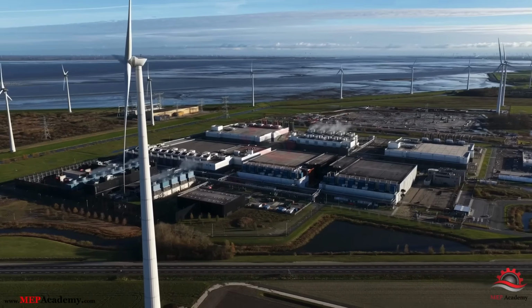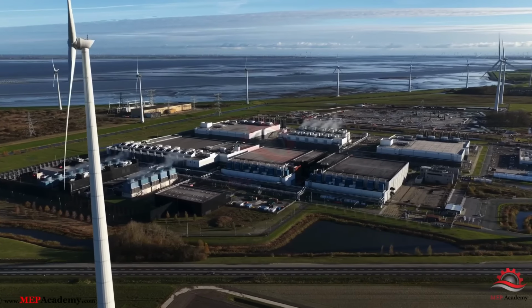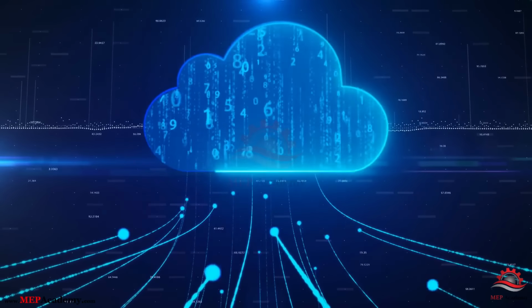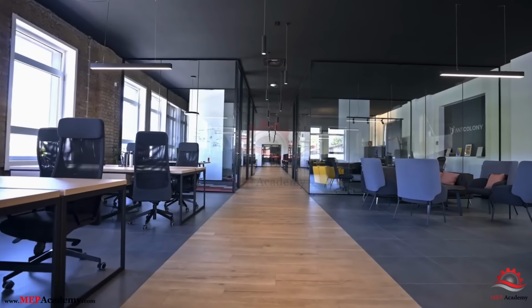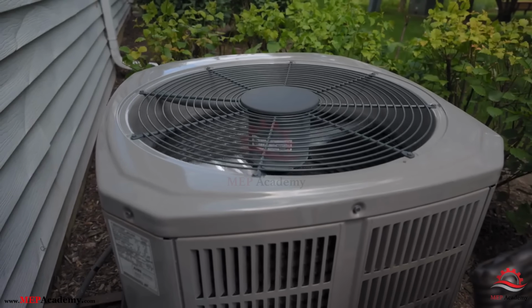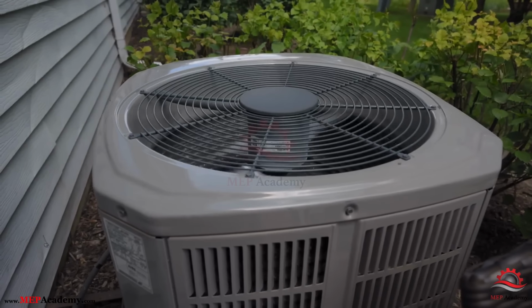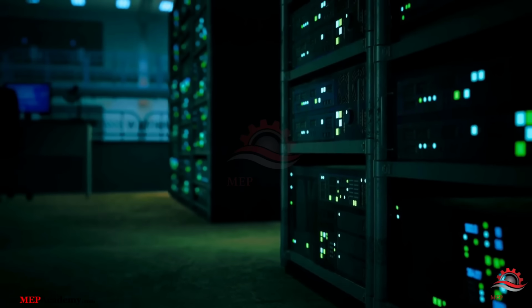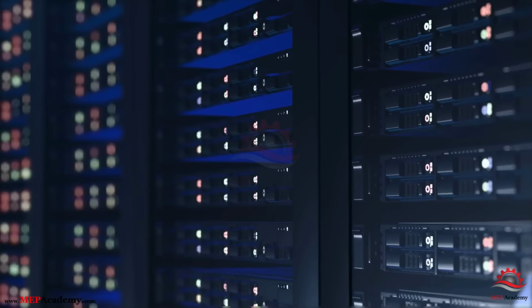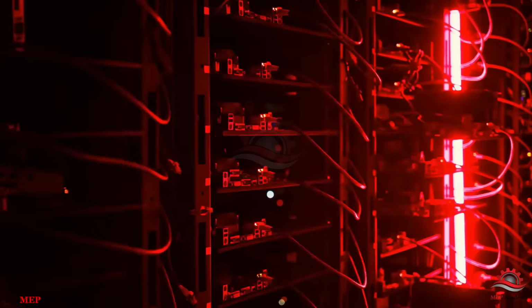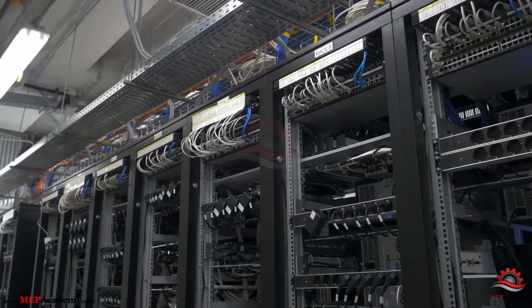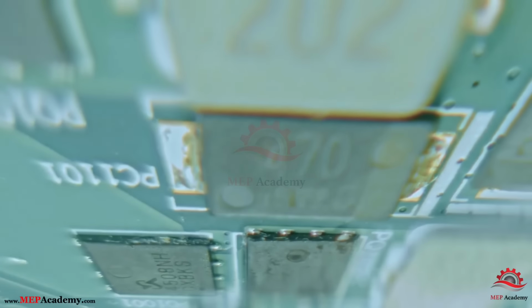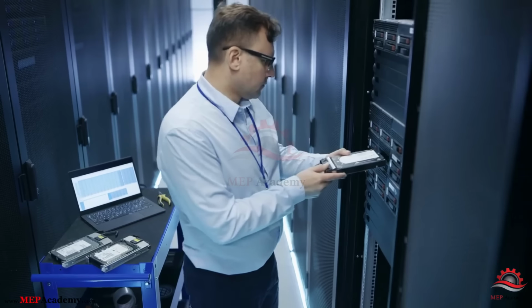Data centers are often misunderstood because they look similar to commercial buildings from the outside, but operationally they are very different. In an office building, occupancy changes throughout the day, cooling loads rise and fall, and equipment cycles on and off. In a data center, electrical loads are constant, cooling demand is continuous, and systems rarely shut down. Failure tolerance is also very different. A comfort cooling failure in an office building creates discomfort. A cooling or power failure in a data center can create immediate operational risk. Because of this, data centers typically include redundant equipment, multiple power paths, and system designs that allow maintenance without shutting the facility down.